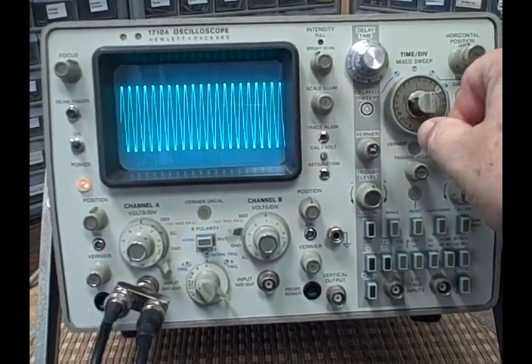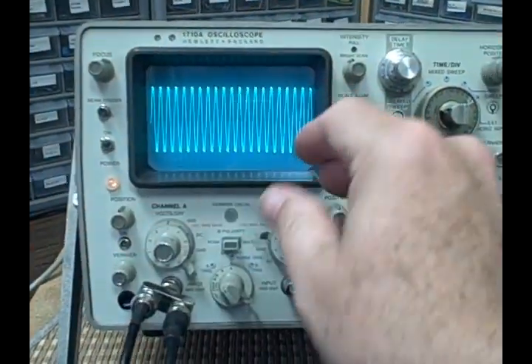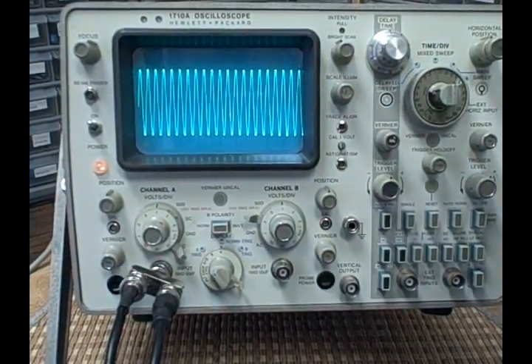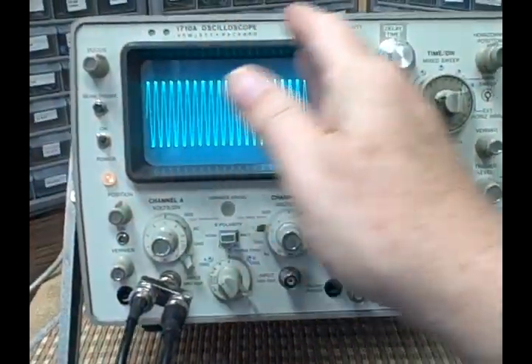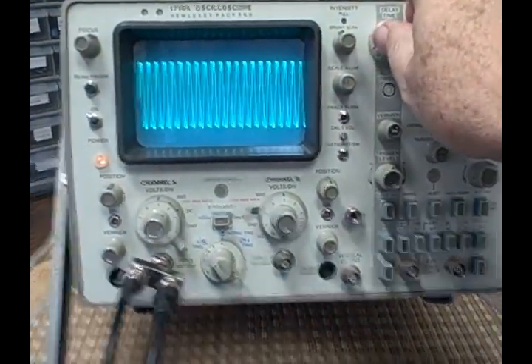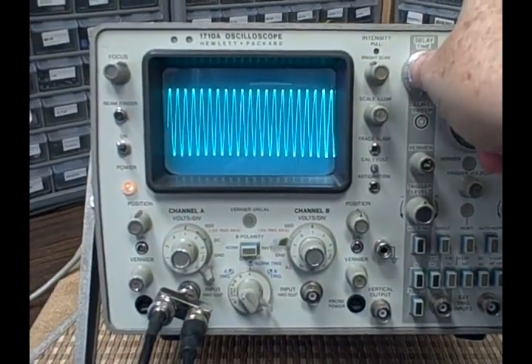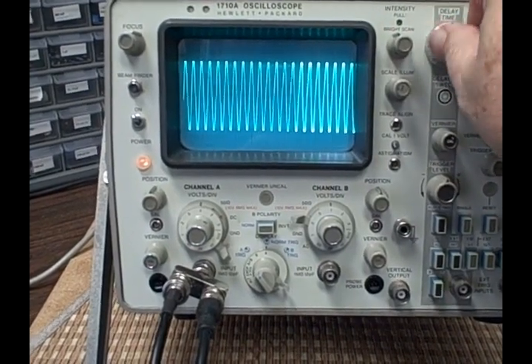If I was to put myself using this center knob here, take myself from main sweep and go to mixed sweep, now potentially what I'm looking at is both the regular main sweep and then a portion of it that is the delayed sweep. However, right now it's all the way off to the right. I take my delayed time knob up here and start dialing it down. As I do, you're going to start to see a brighter image snake its way down across the screen.